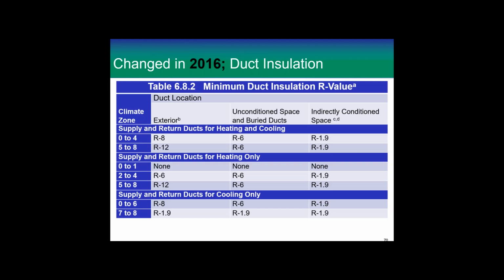Minimum duct insulation values. So this changed in 2016. The table did change. These are minimum values, so sometimes you should use more than this. And they are sorted by exterior, unconditioned space, or buried ducts, and indirectly conditioned space. Indirectly conditioned spaces are plenums and places like that. Now, these are your climate zones, and this is supply and return duct for heating and cooling. This is supply ducts for heating only. This is supply ducts for cooling only.